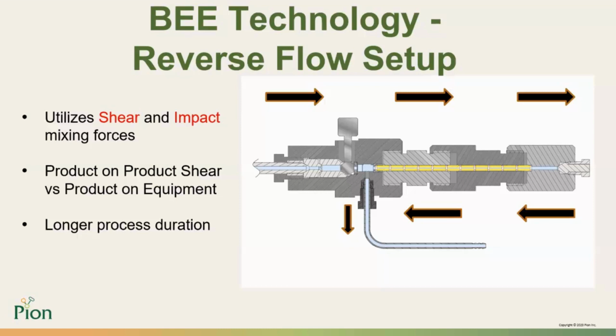The jet stream will impact the plug on the right side of the cell, where the main impact force is felt. It's referred to as reverse flow because this jet stream reverses direction and starts traveling right to left back up the emulsifying cell inside the reactors and seals. As it does this, it contacts the primary jet stream, still exiting the nozzle. These competing streams will collide, leading to direct product-on-product shear, and the product will effectively shear itself. The exit for reverse flow is down at the bottom of the cell, so the longer process duration is defined by the product that will pass through each reactor twice as it travels down and back up the emulsifying cell. Reverse flow is an ideal flow pattern for hard or abrasive materials, cell rupture, or any materials that respond well to high shear mixers.